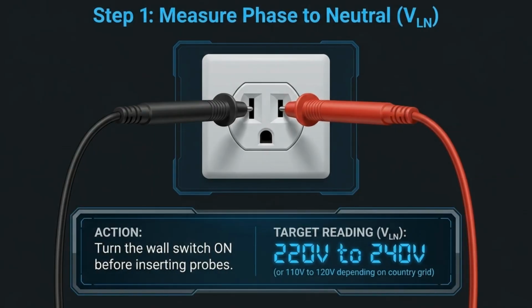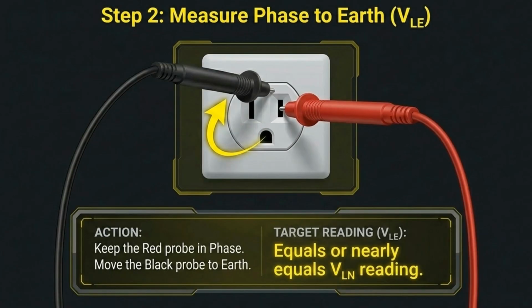Step 1. Measure phase to neutral. Turn the wall switch ON before inserting probes. The target reading, VLN, should be between 220 volts and 240 volts, or 110 volts to 120 volts depending on your country grid.